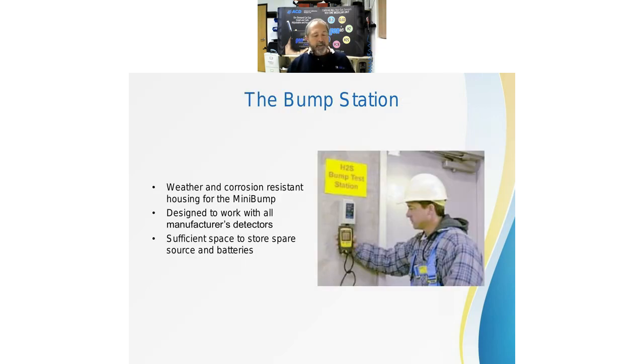There's the bump station. You can buy this thing set up in a hard enclosure so that it's, you know, these are mostly seen in refineries and on ships and things, and so it's set up there. You walk up, you press the button, you hold your gas detector in front of it, it starts to beep, and you walk away. It shuts itself off after 30 seconds, and the next guy coming through, a lot of times they're mounted at the guard shack where you come onto a facility, and they're just bump testing. A lot of times these are used for go, no-go, little sensors that are clipped to the hard hats at refineries and shipyards and things like that.